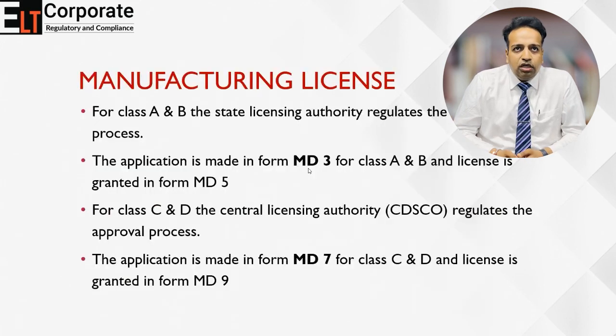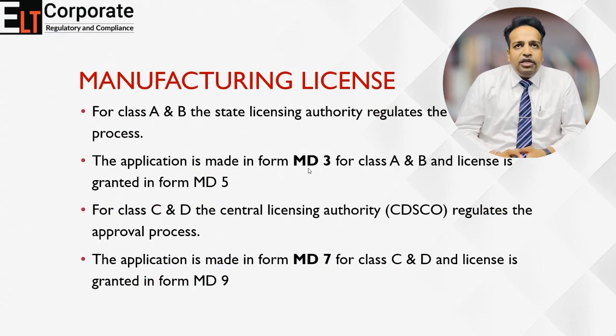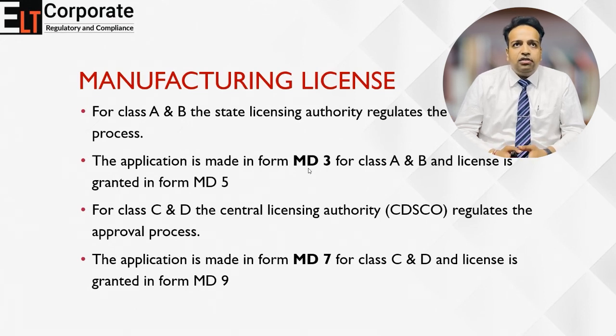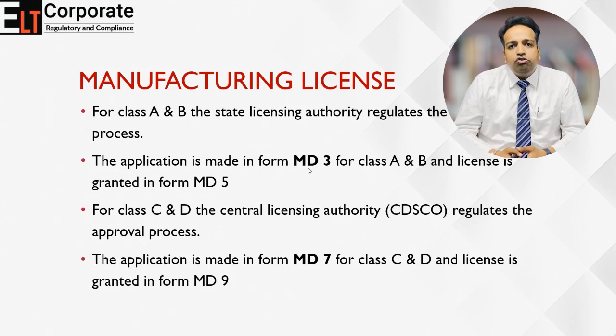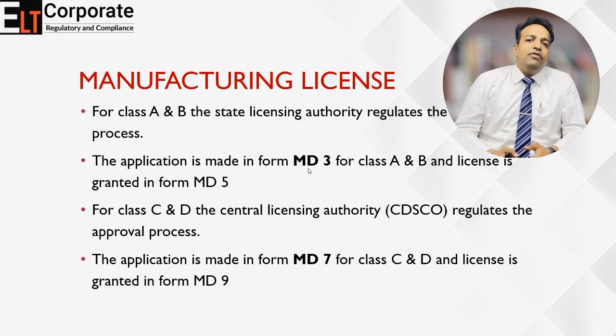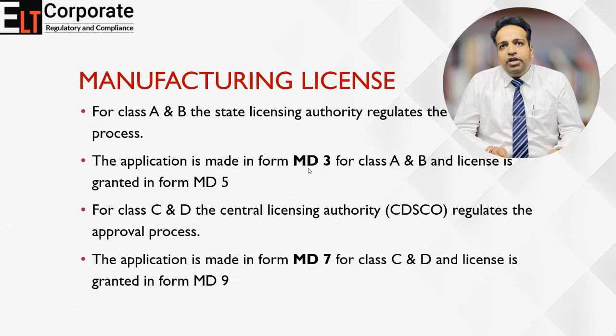For manufacturing Class A and B devices, you need to apply under Form MD-3 and the license is generally granted under Form MD-5. It should be noted that for Class A and B, the state governments are responsible for issuing the manufacturing license. For Class C and D, you need to apply for the manufacturing license under Form MD-7, wherein the government will grant the license under Form MD-9.